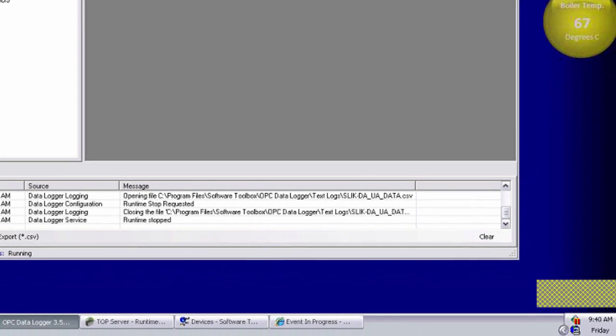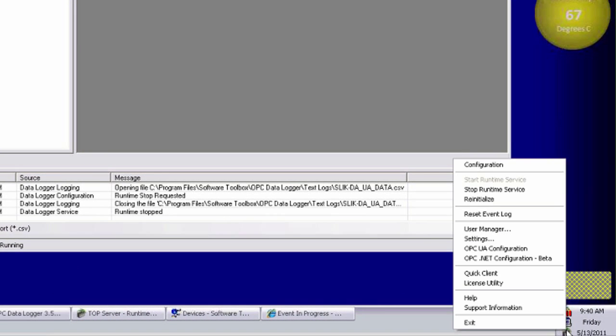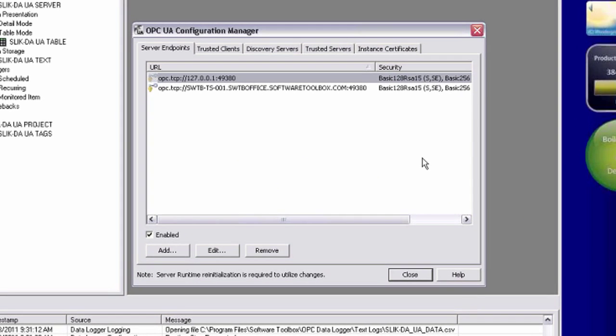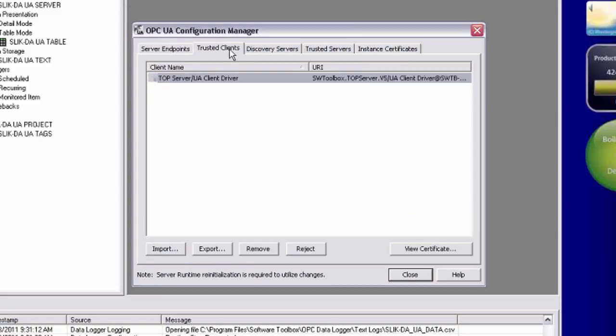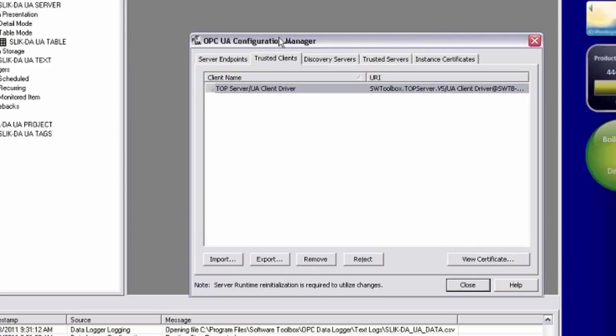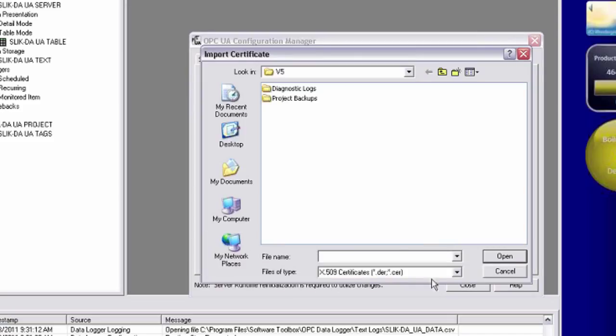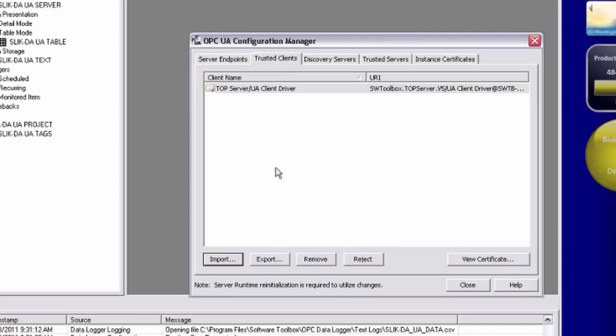The other settings are in the actual OPC UA configuration, which is accessible down here in the system tray via the top server admin icon. So if I launch that, I want to go to my trusted clients. Now here's where I went to import the OPC data logger certificate on my remote machine. On that machine, I basically went to the trusted clients, click the import button, and browse to that file that I copied over from this machine. On that machine, I would see my OPC data logger showing up in this list of trusted clients.